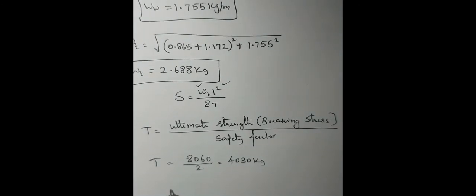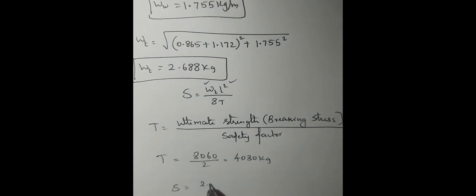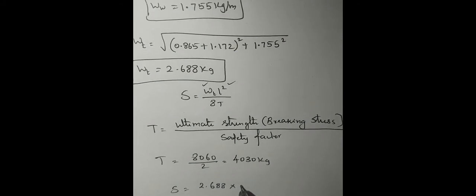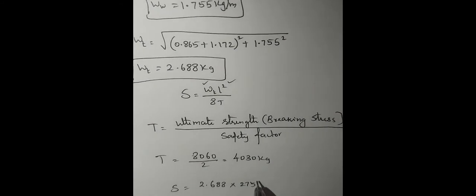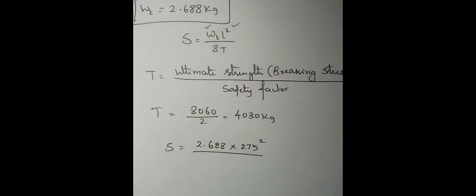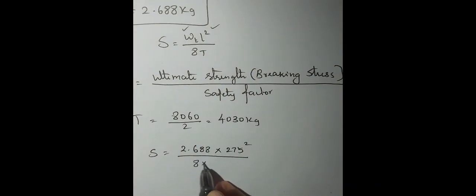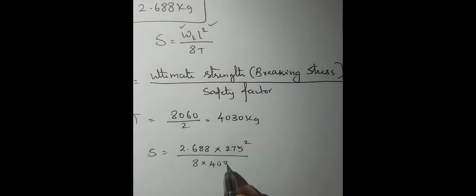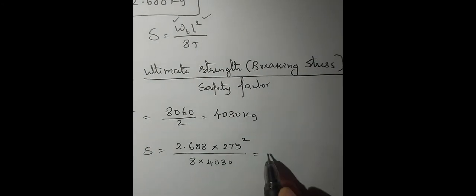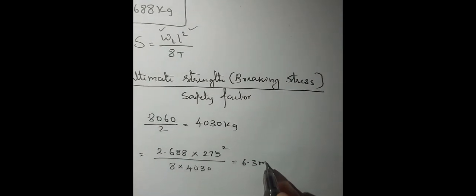Now substituting in the SAG formula: S = (Wt × L²) / (8T) = (2.688 × 275²) / (8 × 4030). Calculating this, we get SAG = 6.3 meters.